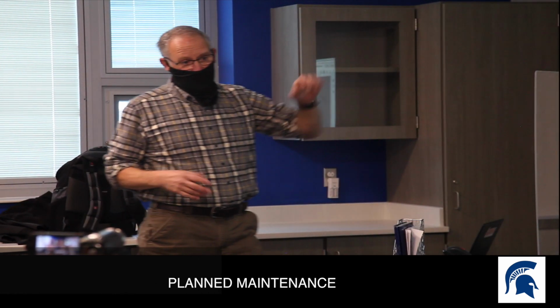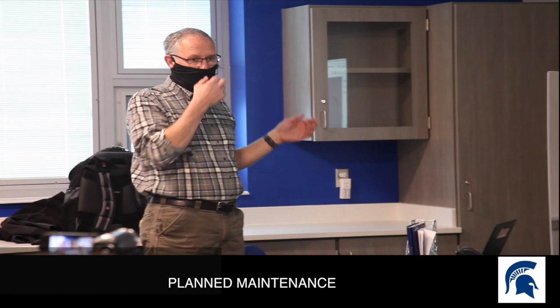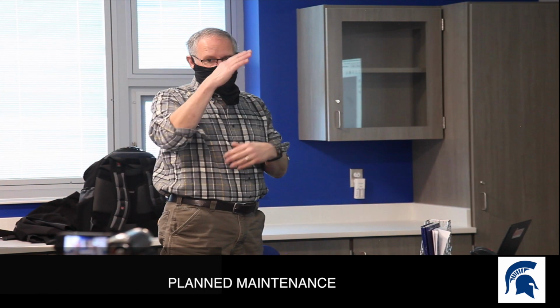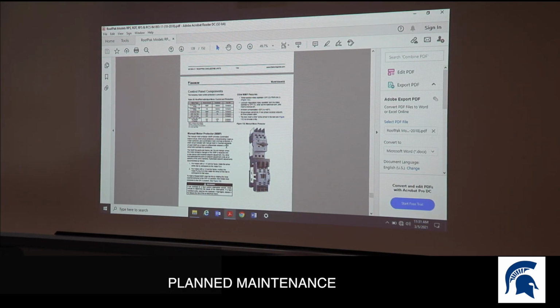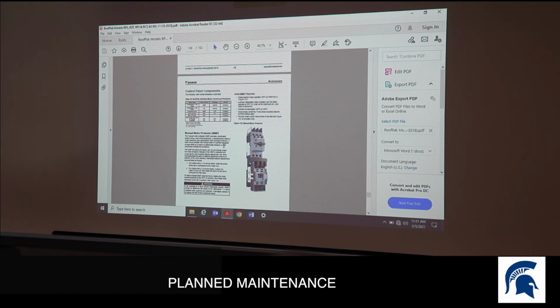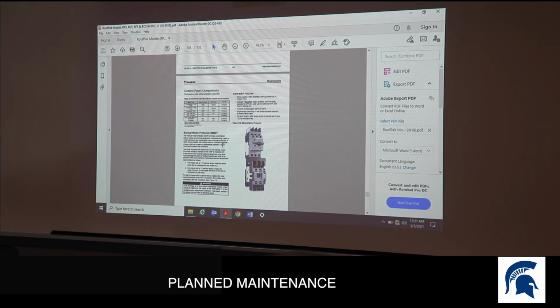They have a whole section about coated coils, but we're not by the ocean, so you don't have coated coils. There's a whole group of cleaners meant for those because of more corrosiveness near salt water. In your case, the garden hose is fine. But it goes back to the same thing: stay ahead of them. It's designed to shed water, it's outside, so there's nothing you'll do on that condensing section that gets water into your building.